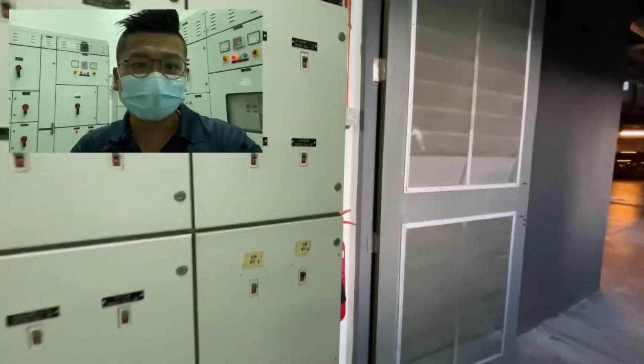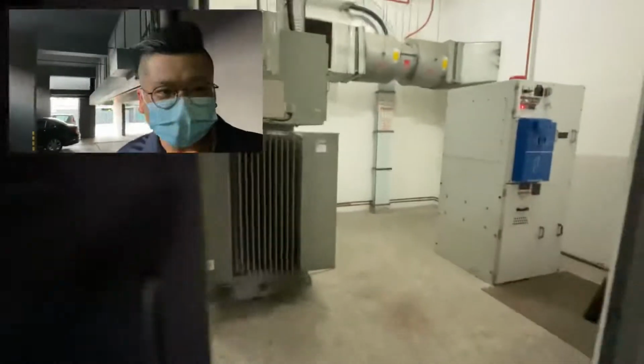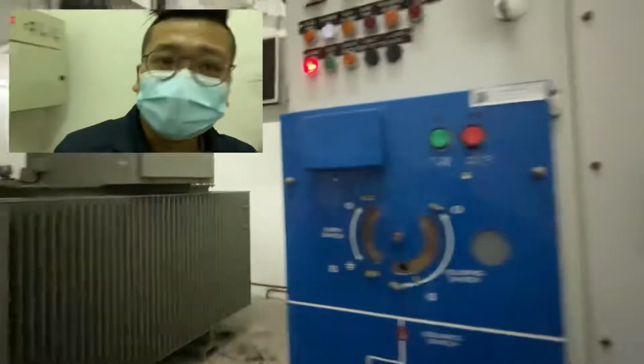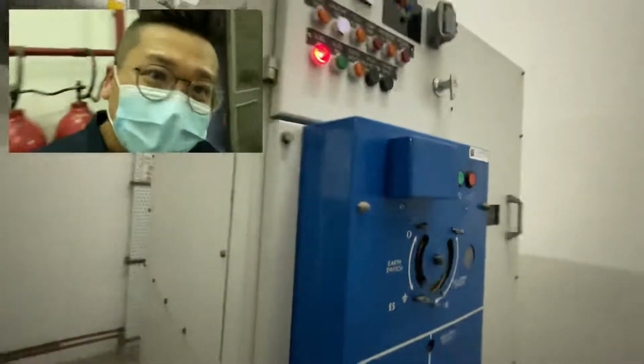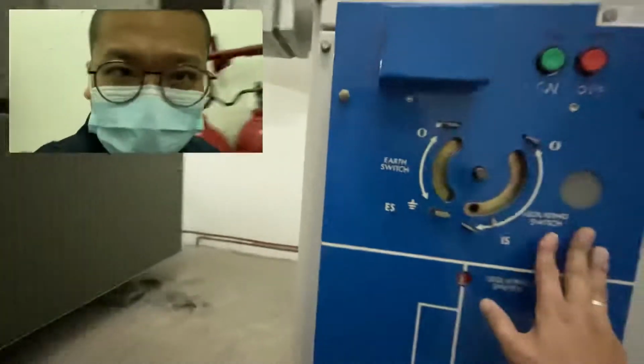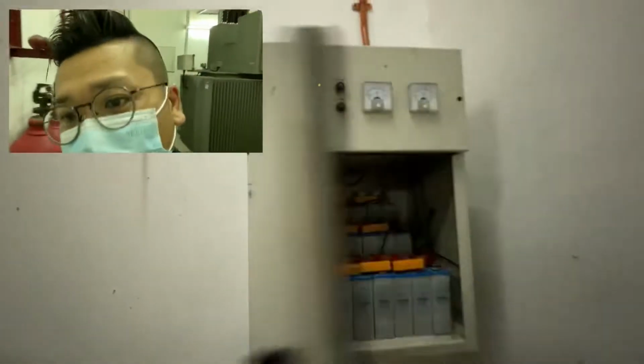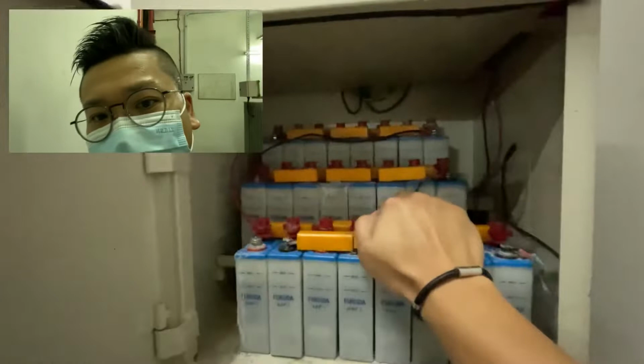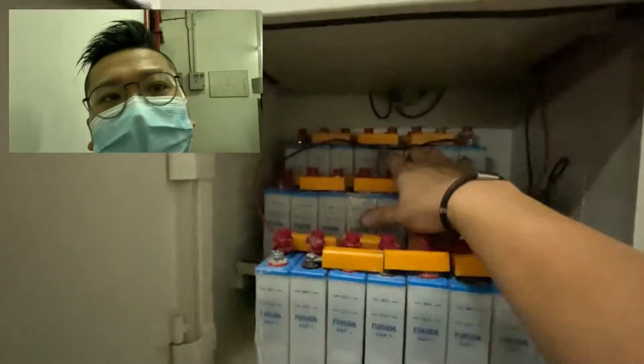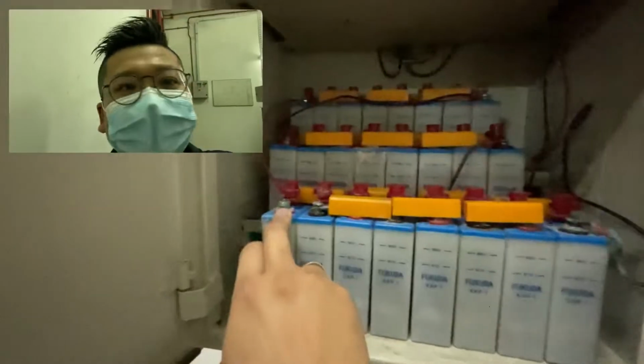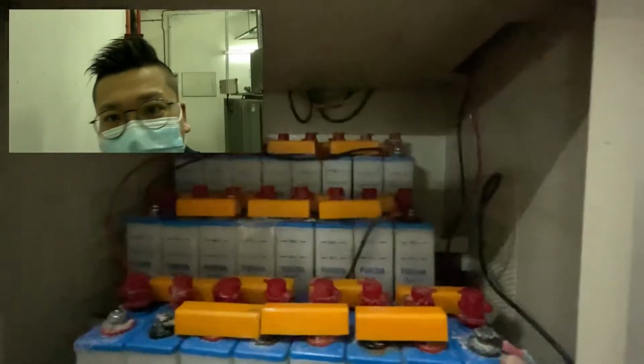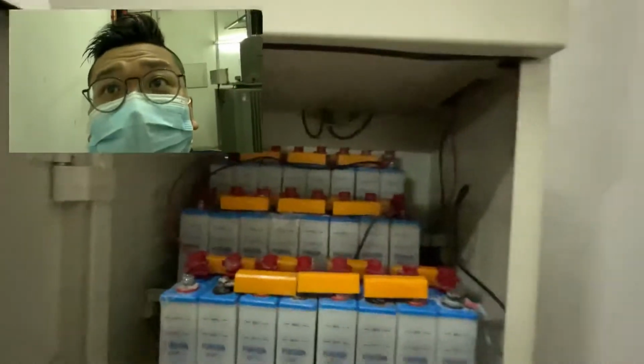Okay, let's walk to other room. Okay, here we have the MSB number 2 transformer room together with the load break switch. This is what we call the load break switch. It's not a switch gear, but it's a load break switch. Inside there's a fuse, and this one come together with a switch, and also there's a breaker. Here we have a tripping unit. So let's have a look at the tripping unit. Okay, need to service because the oxidization is quite a lot here. So I think it's about time.